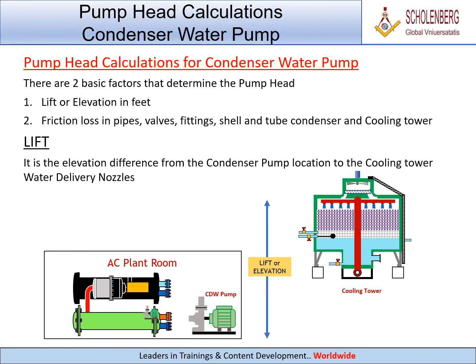Pump head calculations for condenser water pump. There are two basic factors that determine the pump head: 1. Lift or elevation head. 2. Friction loss in pipes, valves, fittings, shell and tube condenser, and cooling tower.